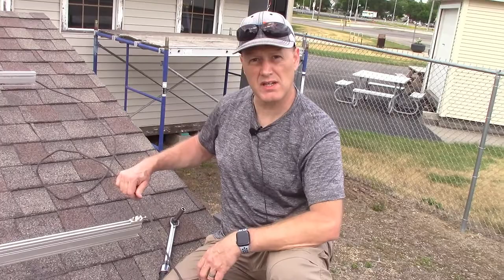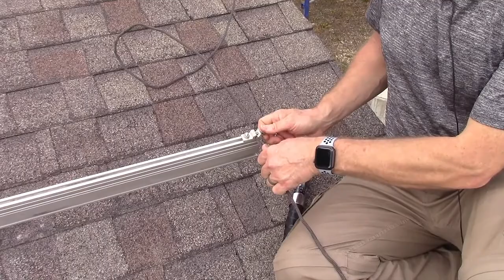We're using this bare copper wire to bond the metal parts of the rack together that are not intended to have electricity on them. In case that we do have a ground fault and electrical current gets on these metal parts of the system, we're going to create a pathway that goes back into the electrical system in the building, and it's grounding there. We're going to tie all of that together so that if we do have a ground fault that is current going on to the metal parts it's not supposed to, it will cause the circuit breaker to trip.